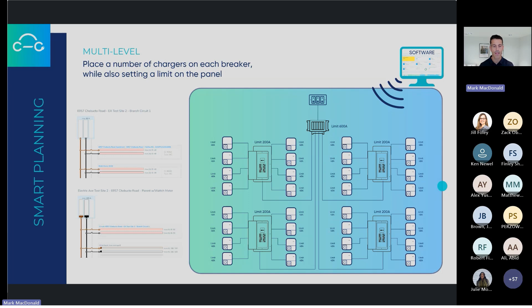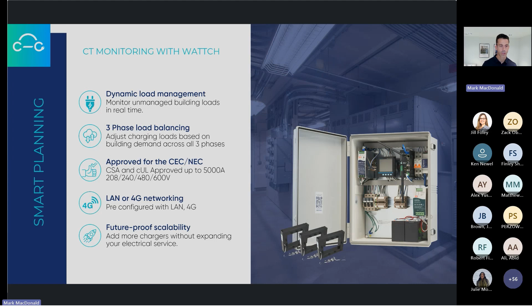If I put an energy monitoring system in place that can communicate with the charging loads and throttle them to 0 during peak times or peak service demand times, then I can 0 rate the EV charging loads in the building. So now as an engineer, I can take an existing multi-unit, I can add 100 chargers, and I don't have to bring in a new service. I don't have to do complex load calculations. Now I'm simplifying this. Obviously, some of this work would still be done as far as calculations. But what this does, we go up to our kit, others do it. Our kit goes up to 5,000 amps on a 3-phase 208, 480, or 600 volt service. And why this works so well is because all of the EVSE, the chargers in the building, we always know how much load they're drawing because they have current transformers built in.